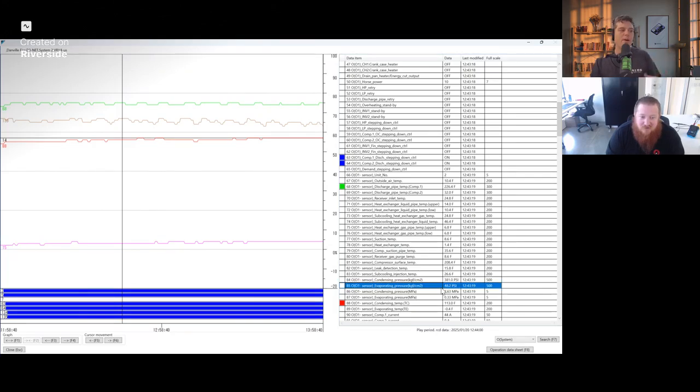Now, again, to Donald's point, we kind of ignore the evaporation pressure because the colder it gets outside, the lower this temperature and pressure is going to be. So again, you're going to find systems where the expansion valve is pegged wide open at -5 degrees outside because it's doing everything it can to survive and to put out heat, which is, I'd love to get some low ambient data from our Canadian brothers and show what it looks like at -10 degrees outside and how much it beats its head against rocks, just so you can see how bad it is.